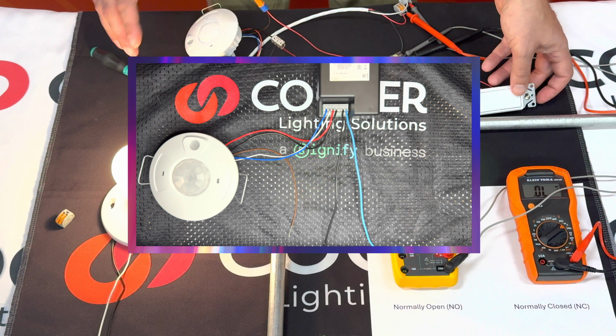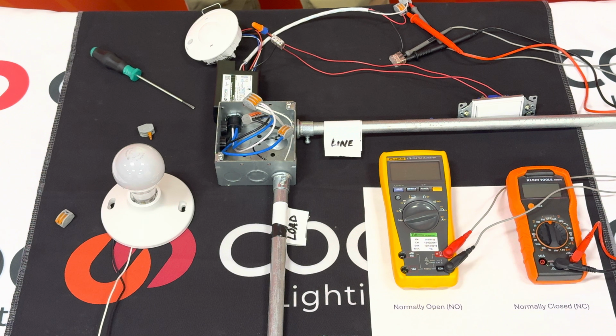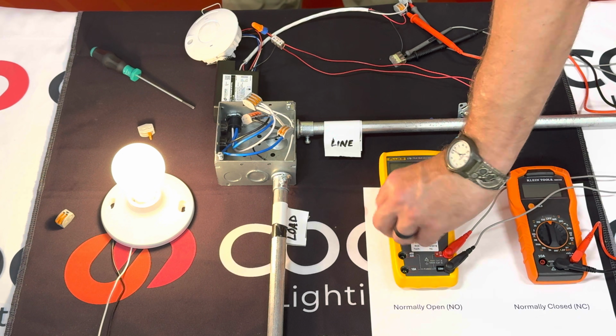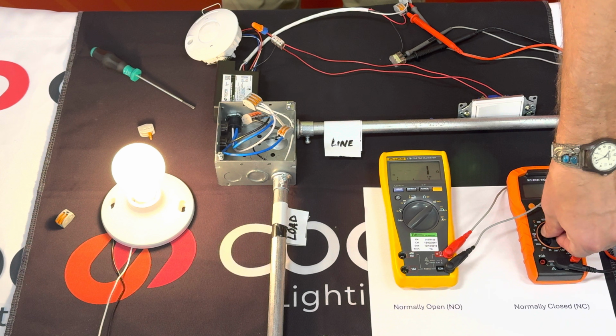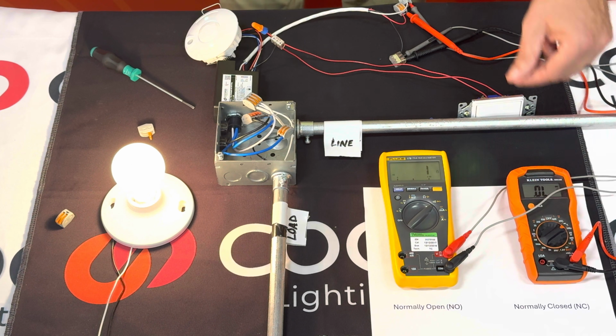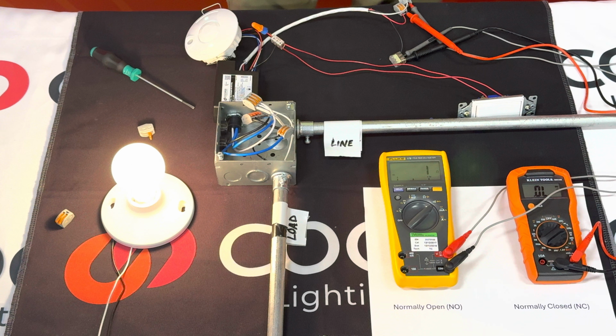In this configuration, when the sensor sees motion, the RSP-V will send a closure to the BAS controller. This closure will remain maintained until the sensor times out due to the space being unoccupied. Testing BAS output from the RSP-V. With a meter set to continuity wired to BASCOM and BASNO, the meter will show a short when the sensor sees motion. If we then meter between BASCOM and BASNC, the meter will show an open.